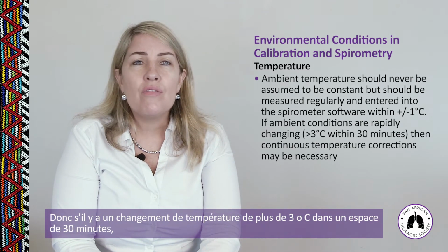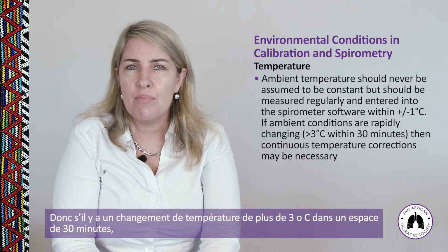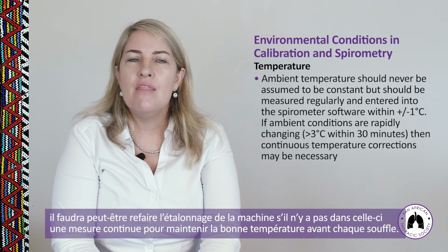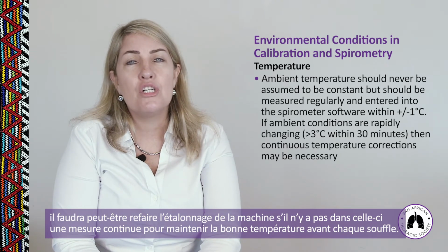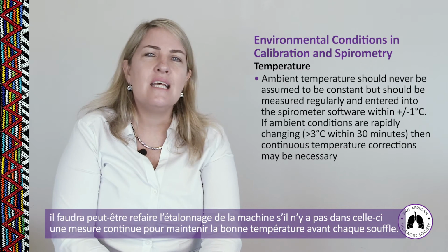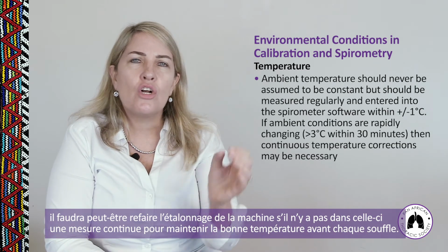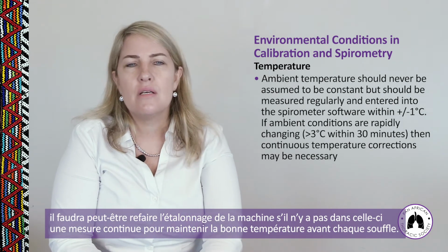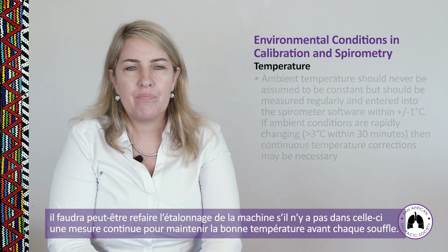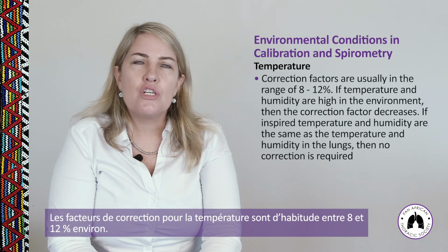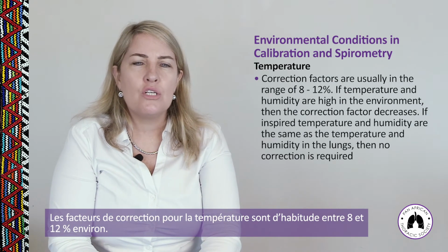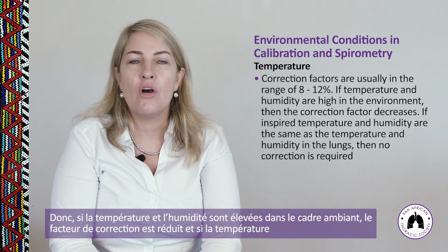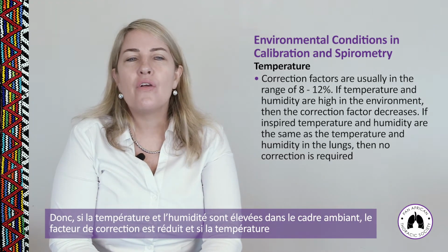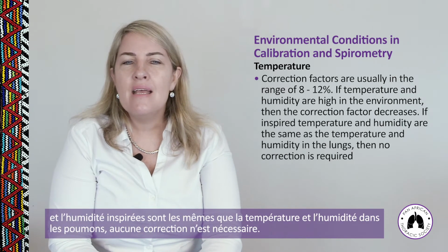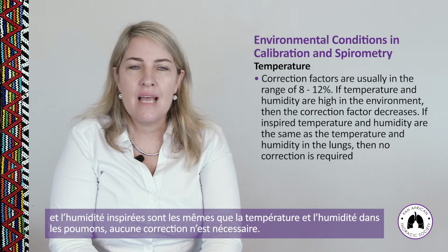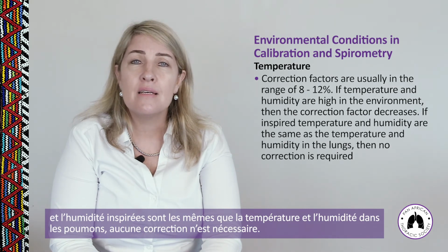So if there's more than 3 degrees Celsius change in temperature within 30 minutes, then you may need to recalibrate your machine if there is not a facility in the spirometer itself to measure continuous temperature corrections before each and every blow. Correction factors for temperature are usually in the range of approximately 8 to 12%. So if temperature and humidity are high in the environment, then the correction factor decreases. And if inspired temperature and humidity are the same as the temperature and humidity in the lungs, then no correction is required.